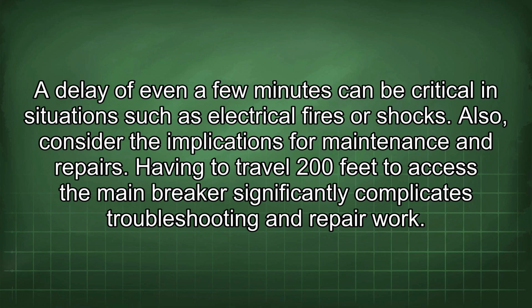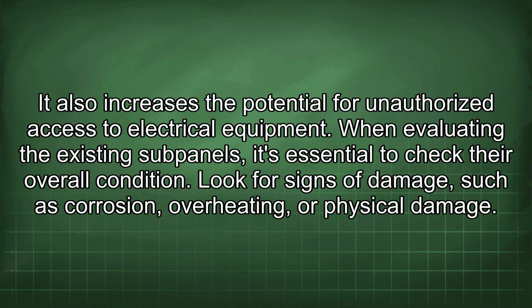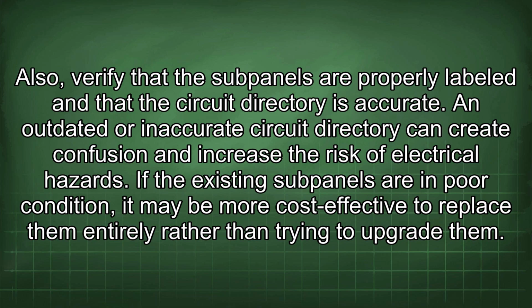Having to travel 200 feet to access the main breaker significantly complicates troubleshooting and repair work. It also increases the potential for unauthorized access to electrical equipment. When evaluating the existing subpanels, it's essential to check their overall condition. Look for signs of damage, such as corrosion, overheating, or physical damage. Also, verify that the subpanels are properly labeled and that the circuit directory is accurate. An outdated or inaccurate circuit directory can create confusion and increase the risk of electrical hazards.